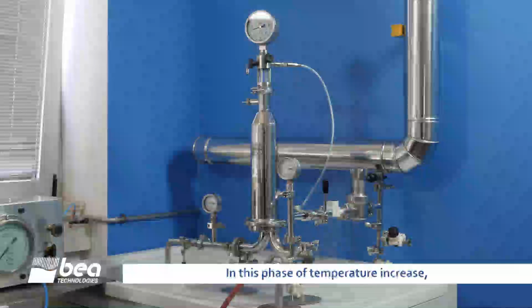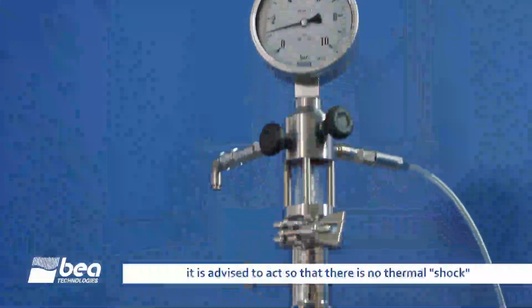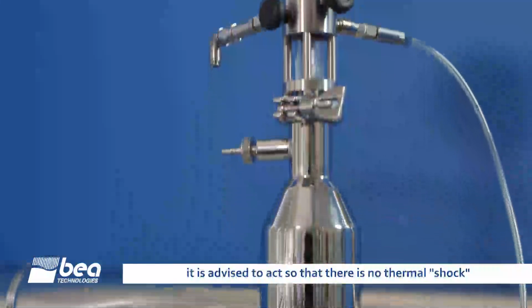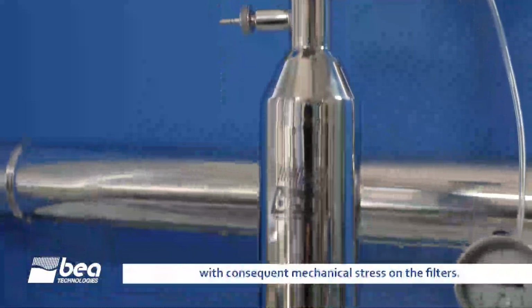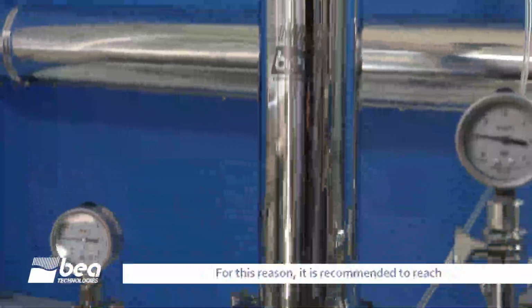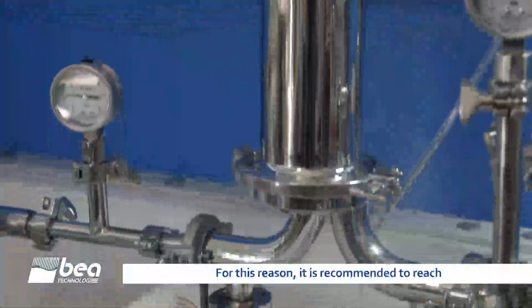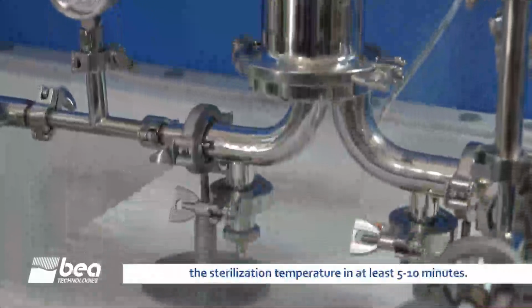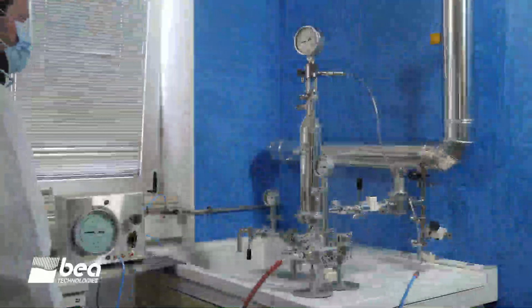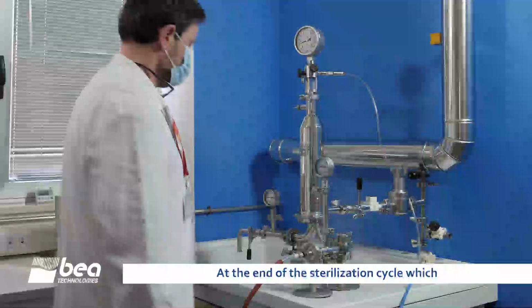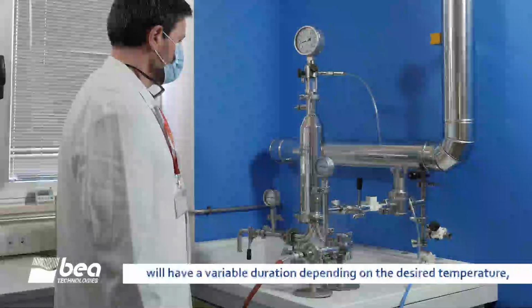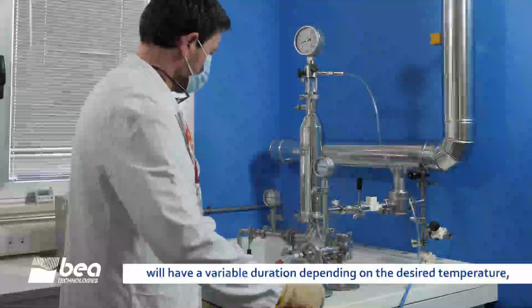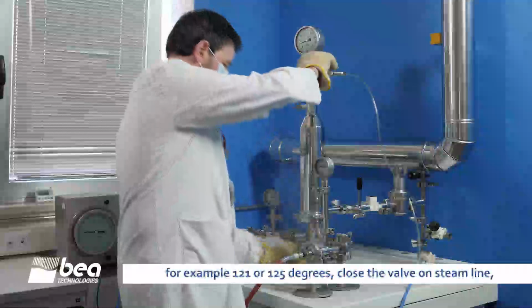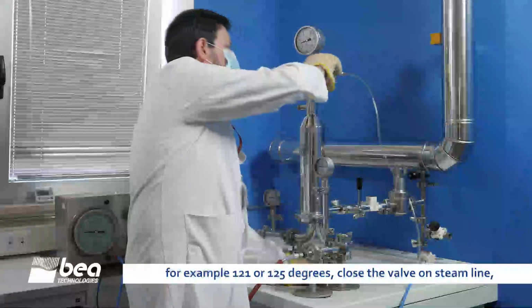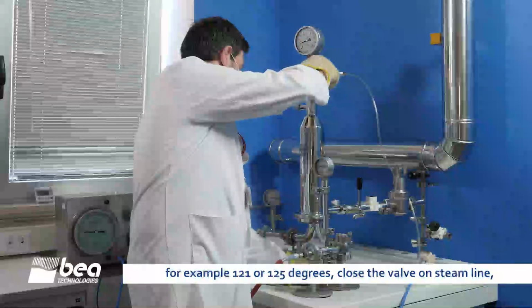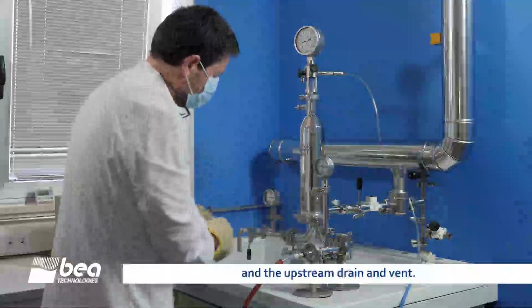In this phase of temperature increase, it's advised to act so that there is no thermal shock with consequent mechanical stress on the filters. For this reason, it's recommended to reach the sterilization temperature in at least 5 to 10 minutes. At the end of the sterilization cycle, which will have a variable duration depending on the desired temperature, for example 121 or 125 degrees, close the valve on the steam line and the upstream drain and vent.